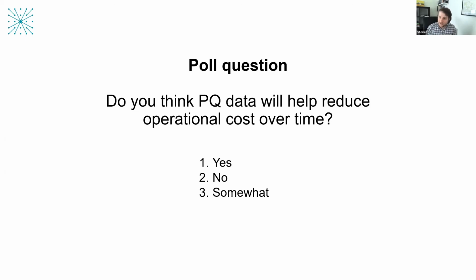I don't think is any kind of stretch at all, is that we can very precisely and confidently monitor any kind of aberration in the voltage. So if there's, for example, a transient overvoltage, we can detect that and log it, and we can, for example, log how many of those happen for each asset over a certain period of time. So you could say there were 20 of those last month, for example, and we can also build up a kind of history of that asset, of what harmonics it experienced, and we can probably weight that for certain harmonics which are more likely to cause damage. So these are the things that we can build up. It's basically just an asset health history for each asset that we monitor.